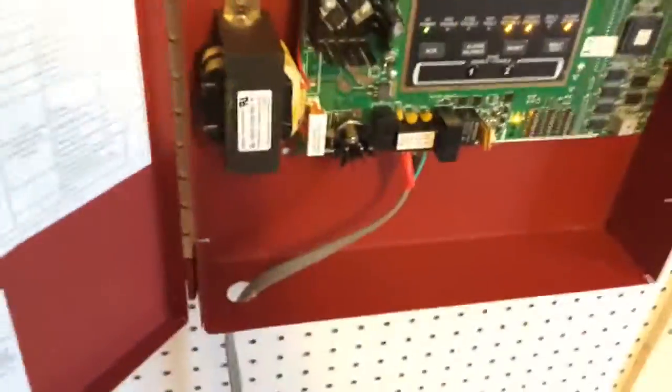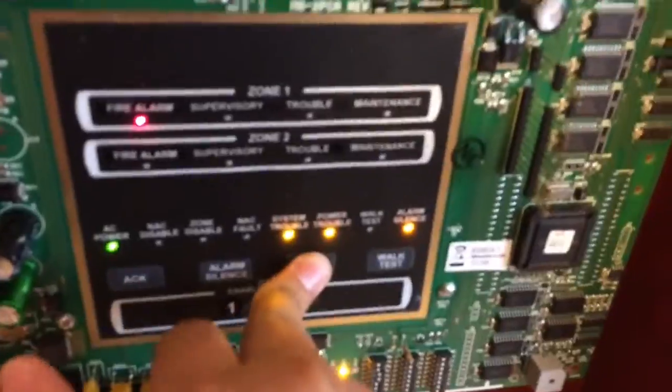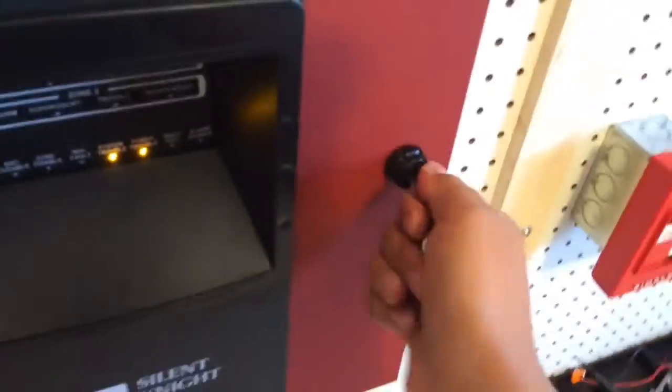I know someone in the instructions said not to connect it to a pulsing NAC circuit — well, whoops. I haven't damaged anything though. Here's the inside of my panel: NAC connections, zone connections, all the other ones are unused. There's a transformer that I'm not happy about because it outputs FWR, which means I can't use Simplex on it.